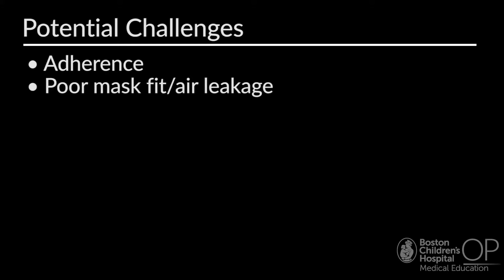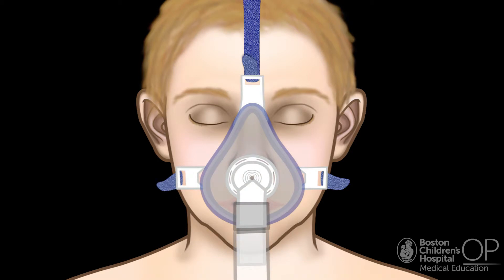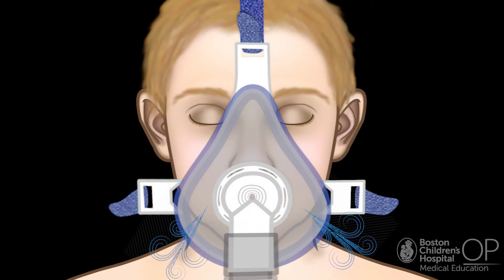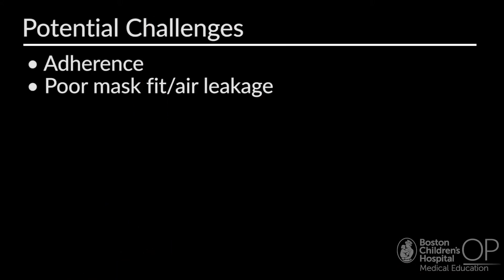Another potential issue with BiPAP and CPAP in the home is poor mask fit or air leakage. You should feel air coming out of the vents on the side, which is exhaled carbon dioxide, but you shouldn't feel air escaping from where the mask is touching the skin. This can be particularly challenging with children who have craniofacial anomalies — this is also one of the issues Jack's family has faced. Another potential issue is skin breakdown. Alternating between two different types of masks can help prevent irritation, and families can also use a silicone foam dressing as a barrier.